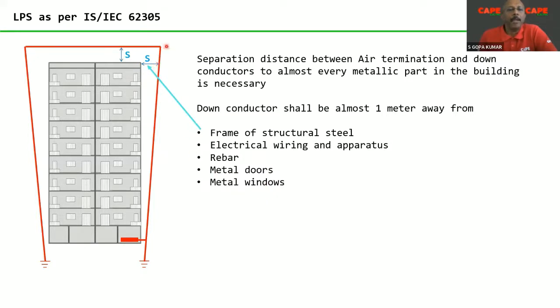Basically, in order to avoid flashover, say for example a lightning strike hits this corner of the building, due to the surge impedance of the down conductor there can be a flashover from the air termination to the building. There can be several flashovers at several locations of the building. In order to avoid flashover, technically, we keep the air termination and the down conductor physically away from the building at a separation distance. So it's very easy to understand.